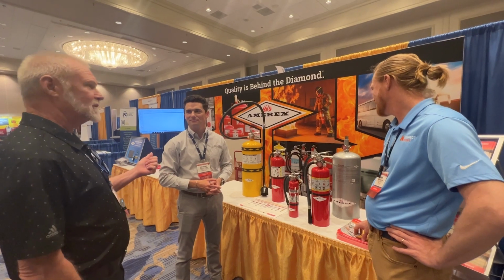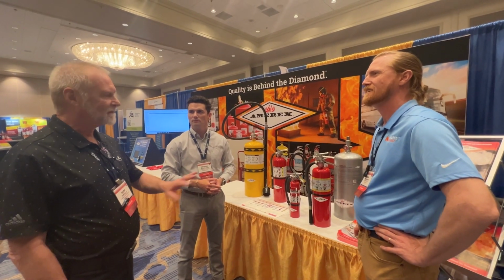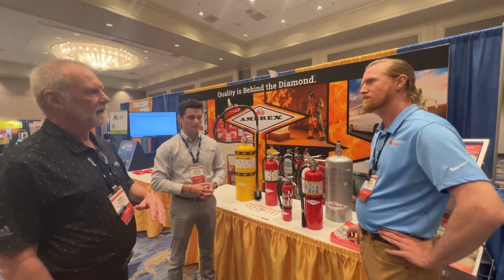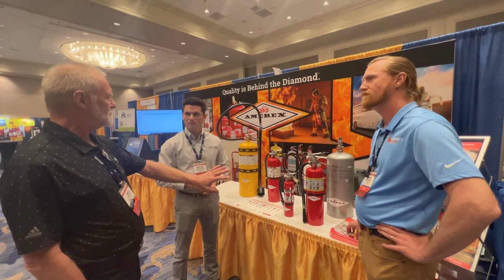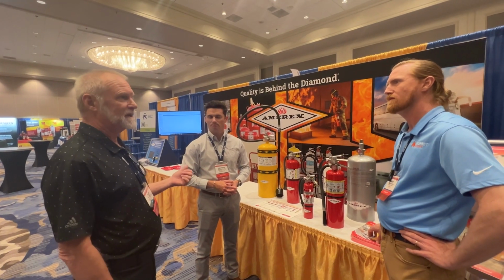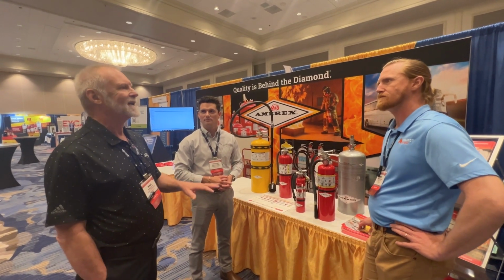And while we were doing this webinar, Brayden asked me, okay, where are you putting these? What type of application are you asking your customers to use them in? And so for me, it was like, okay, because we make these in ABC and Purple K, right? And the 10 pounder is brand new, right? It's the smallest one, but we make a 13 pound, 6 kg, 20 pound, and 30 pound. We make them in compliance flow, like Brayden mentioned a minute ago. We make them in a fast flow product, right? So it kind of meets every different hazard that's out there.